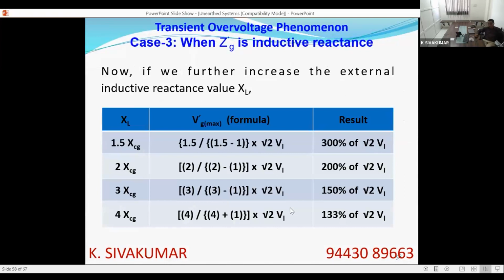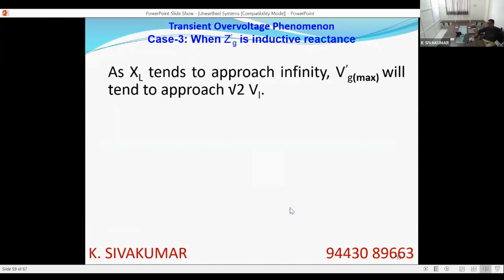Further, if you keep on increasing it, you see it starts coming down. It is like an inverted parabolic curve, starts from a low value, goes to a peak and comes down. So if it is 1.5 XCG, it is 300%, 2 XCG, it is 200%, 3 XCG, it is 150%, 4 XCG, 133%. So if you keep on increasing, it will start dropping down. So at one particular resonance, it will be high. When you make it infinity, again as seen in the case of resistance and capacitance, it will come back and settle down at root 2 VL. So the danger here is whenever the system network inductive reactance is equal to capacitive reactance during an earth fault, there will be a very high overvoltage thrust on the system, which is not good for the system.